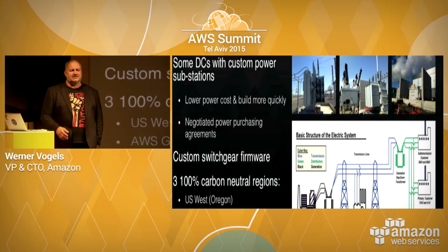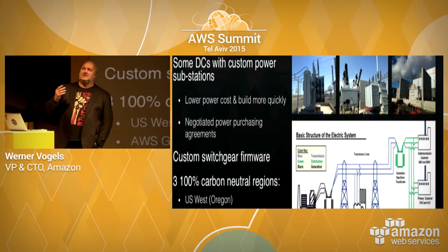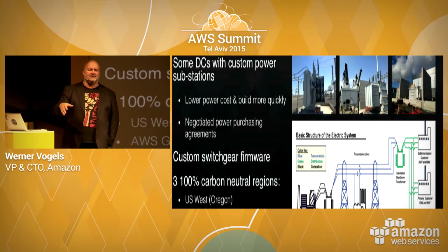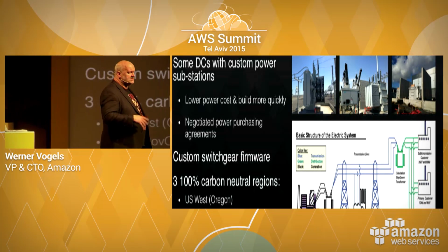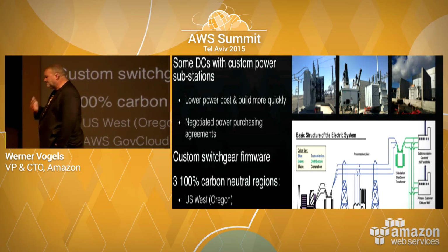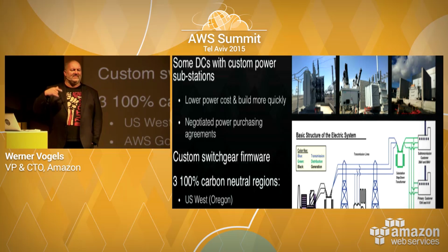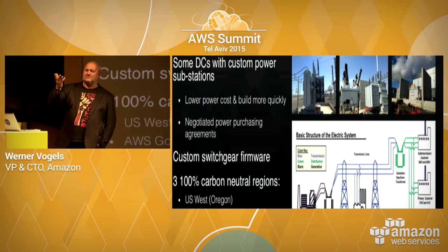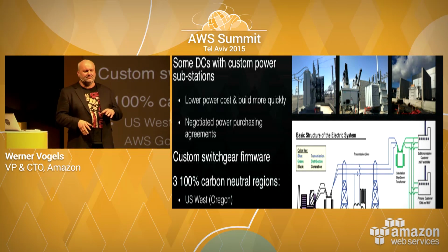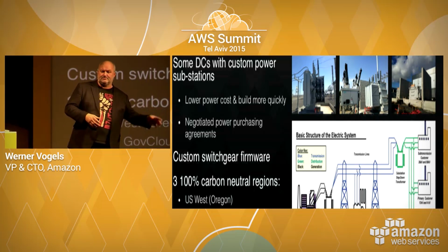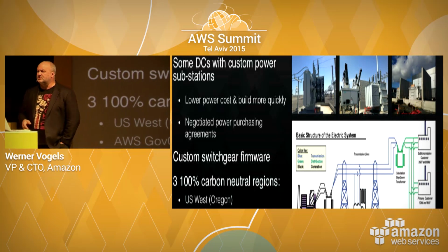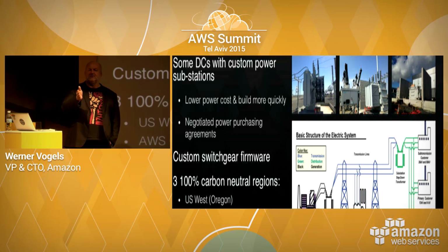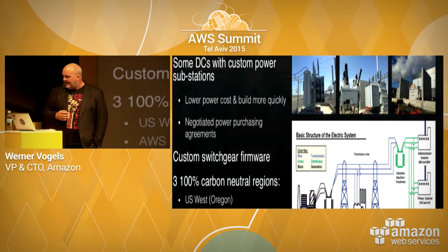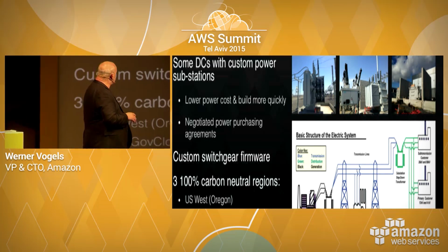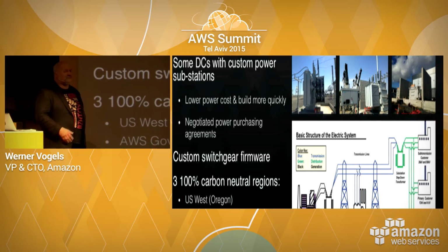A good example: we had one outage, or rather we didn't have an outage. Lightning hits a transformer somewhere that takes away the power coming into the data center. We go over onto diesel—there are multiple diesel generators per data center. Then in one of those data center rooms, the fan is turning not fast enough for some reason. Temperature in that room rises, and the generator shuts down automatically. But we've built a system so it can fail over to a backup of the backup generator. On the servers themselves and under the server racks, we innovated so we can switch in microseconds between two power sources without the servers going down.